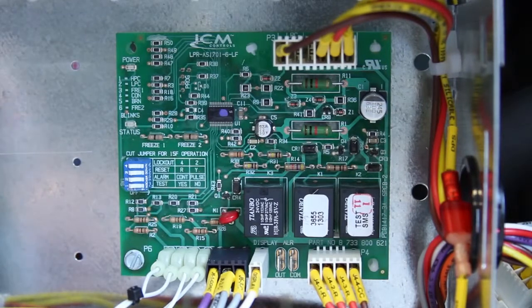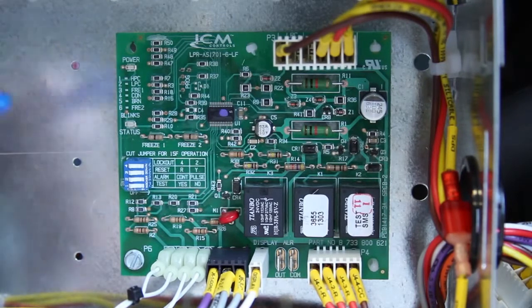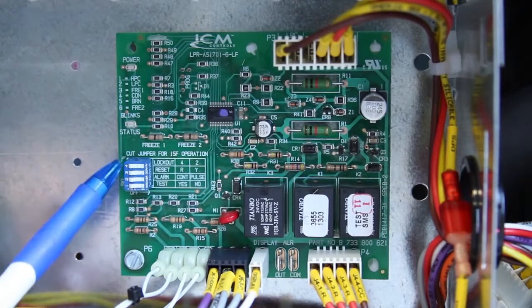Like the TA series, the UPM is equipped with intelligent reset. If any of the safeties open, the unit will go into a soft lockout. It can go into a soft lockout 2 times in a 60-minute period, and then the unit will go into a hard lockout. You can also set it to have 4 soft lockouts in a 60-minute period instead of 2 by moving dip switch number 4 to the left-hand position.